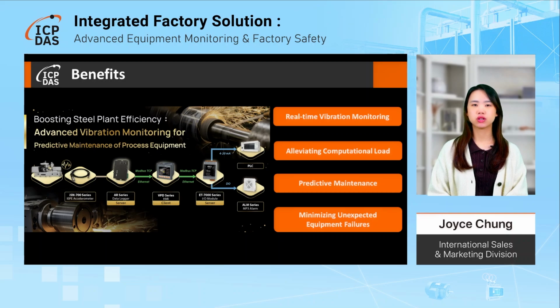The AR400 accelerometer data logger plays a key role in vibration monitoring by capturing raw vibration signals and calculating critical vibration features along with fast Fourier transform spectrum values. This data is seamlessly transmitted via the Modbus TCP protocol to controllers and HMIs for further integration, enabling real-time monitoring without overloading other control systems.